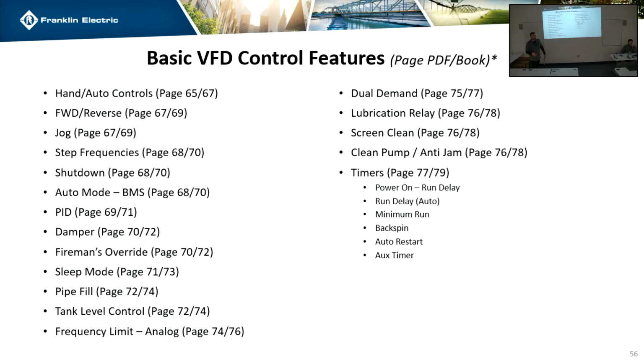Yeah, what we're going over now is more of a design thing. So you have to decide: do you want this to go across the line on a bypass contactor, so it's just going to flood the stairwell, or do you actually want to maintain a pressure so that people can still open doors and get out? No, that's fine. I didn't know if you said that it does automatically change. It does not automatically. Yeah, it's one or the other. It's just an optional programming thing that you can use.